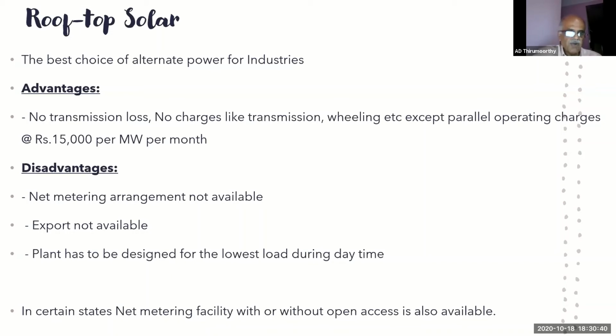Now, what are the disadvantages in this scheme? Net metering is not available here in Tamil Nadu, particularly for HT industries. So export is not available. You cannot export power; you have to provide a reverse power flow relay in case generation exceeds the load, and you have to curtail your generation.